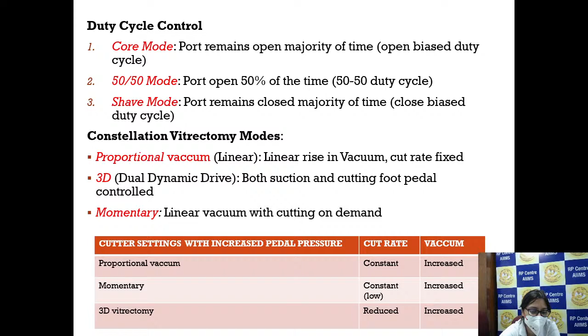In cases of 3D, both suction and the cut rate can be controlled with the foot pedal. But in cases of momentary, when you press the foot pedal, the vacuum will increase linearly, but the cutting is only on demand when you press on the side kicks. So we can see in cases of proportional vacuum vitrectomy, the cut rate is constant, and vacuum is increased. In cases of momentary, the cut rate is usually kept low, because in momentary the cutter usually acts like a scissor and the vacuum is increased with the help of the foot pedal. And in case of 3D vitrectomy, the cut rate reduces when you press the foot pedal and vacuum increases correspondingly.